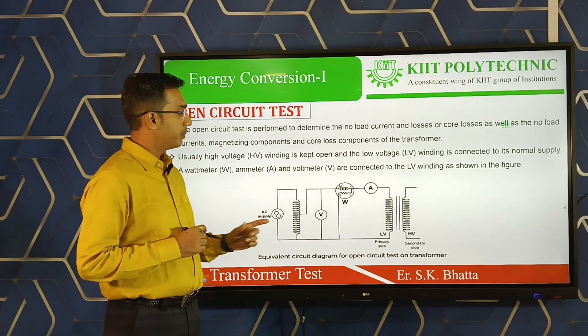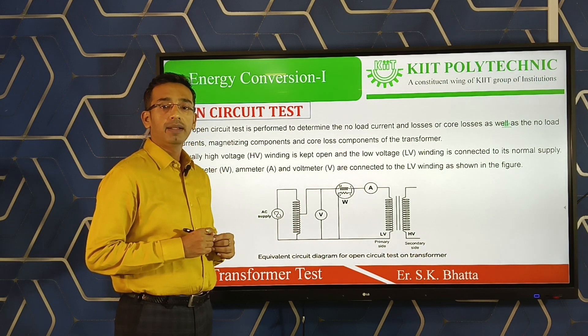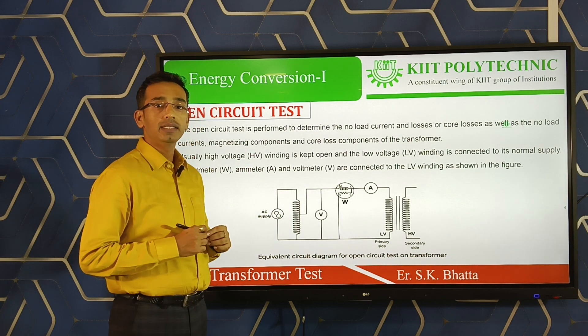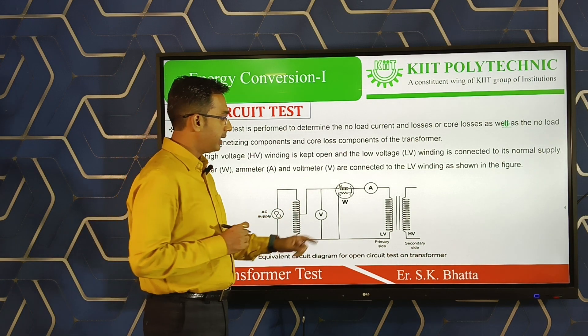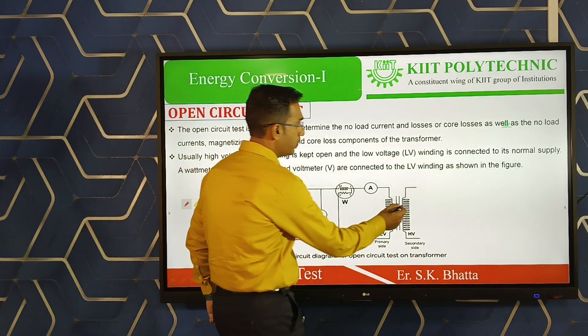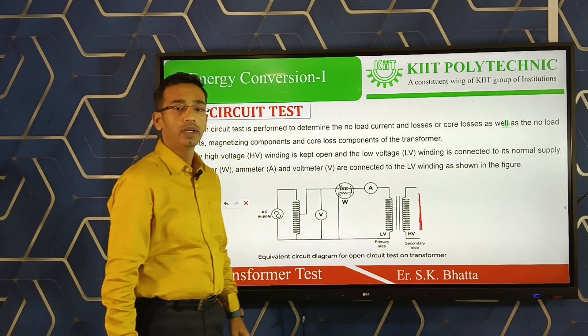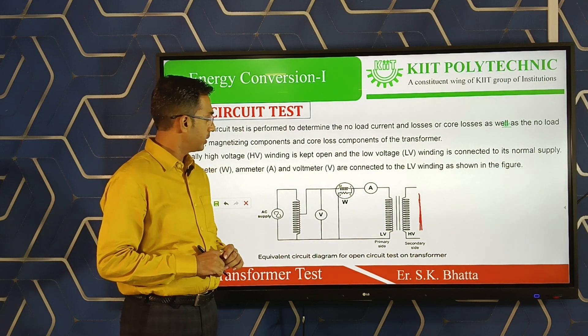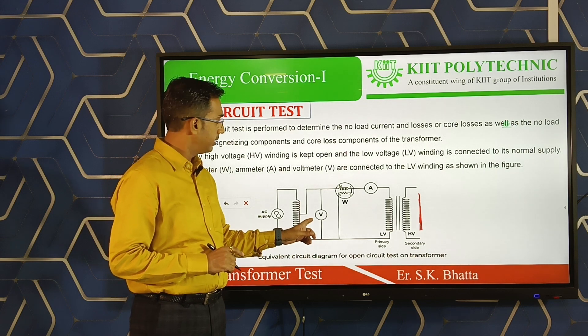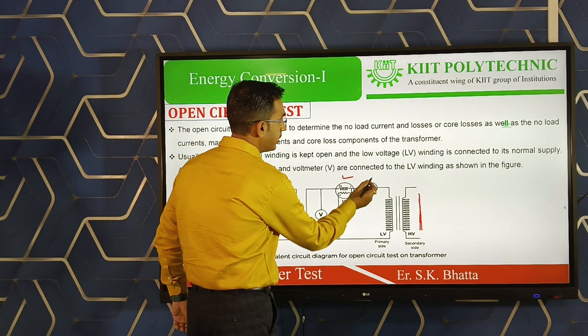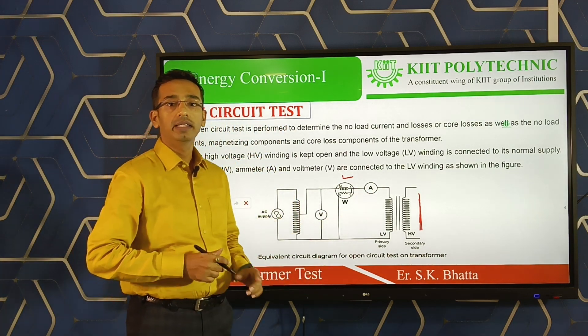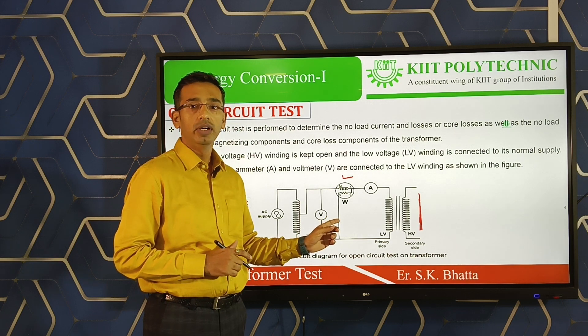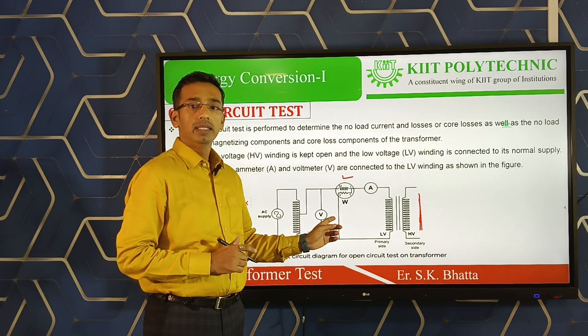Looking at the diagram, this is a single-phase transformer. The primary side is the LV side (low voltage side) and the secondary side is the HV side (high voltage side). As the name suggests, in the open circuit test the secondary HV side is left open. On the primary LV side, instruments are connected: a voltmeter in parallel, a wattmeter, and an ammeter in series.